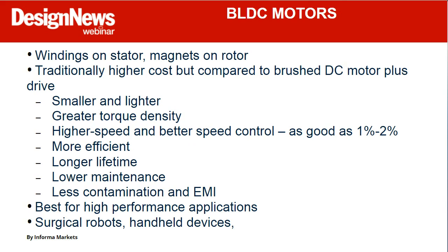On the other hand, brushless DC motors are kind of becoming ascendant in the medical industry, although I am a big believer in different horses for different courses. But BLDC kind of flips the brushed DC on its heel, or on its ear. Again, there are no hard and fast designs, but with the BLDC, we'll go with, typically you're going to have your windings on the stator on the outside, and you're going to have your magnets on your rotor.